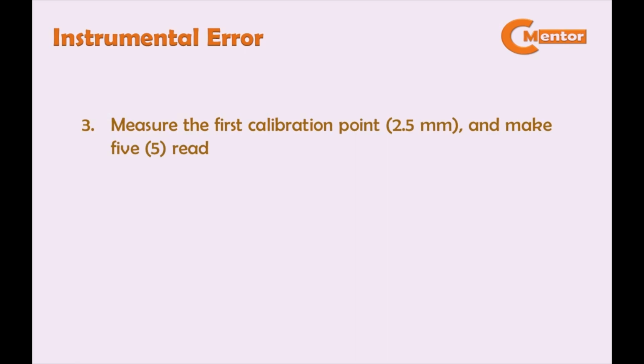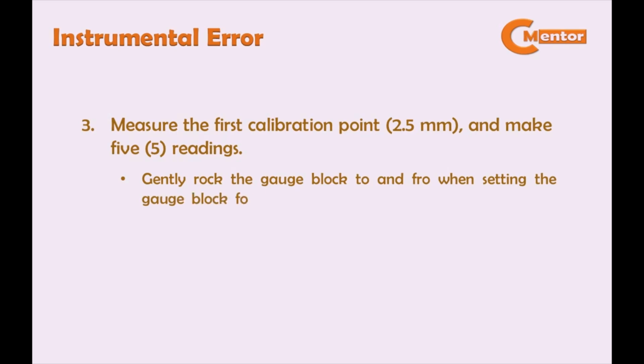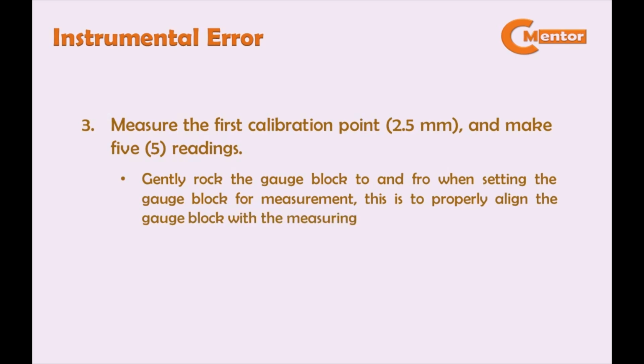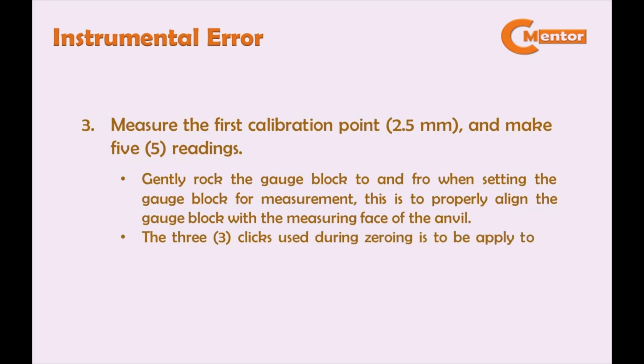Third, measure the first calibration point 2.5 mm and make 5 readings. Gently rock the gauge block to and fro when setting the gauge block for measurement. This is to properly align the gauge block with the measuring face of the anvil. The 3 clicks used during zeroing is to be applied to all calibration points during measurements.